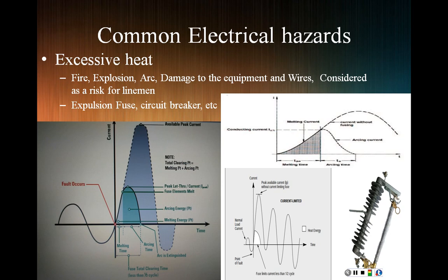We should use equipment like fuses and circuit breakers. They have the same function as in low voltage, but they are different because this is high voltage. The expulsion fuse, the one at our bottom right, is used to avoid short circuits. You can see the graph for short circuits, what happens, and the function of the fuse. If a short circuit happens, the current just increases to a peak.